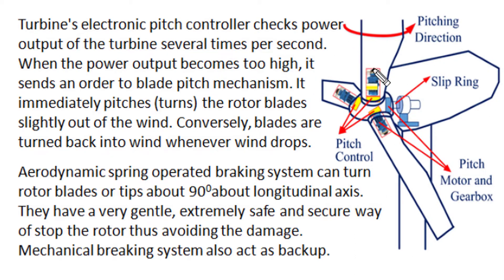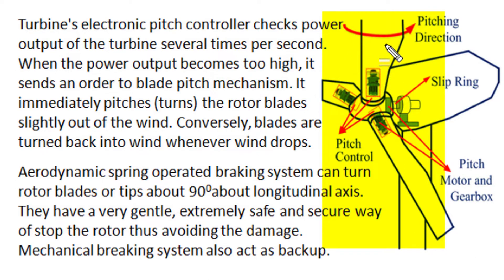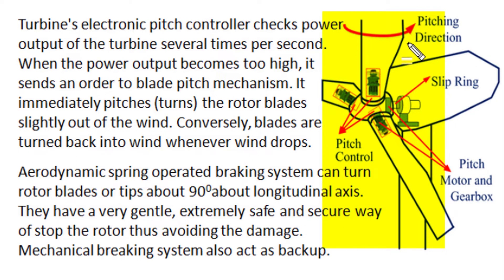Wind turbines also possess aerodynamic safety provisions against over-speed of turbine blades, which may arise when wind velocity suddenly increases to very high values, or when an electrical fault stops the output supply to the grid. In all such over-speeding conditions, a spring-operated aerodynamic braking system is provided, which can turn the rotor blades or blade tips by about 90 degrees about the longitudinal axis. This ensures minimum mechanical impact on wind turbine blades, providing a very gentle and secure way to stop the rotor.